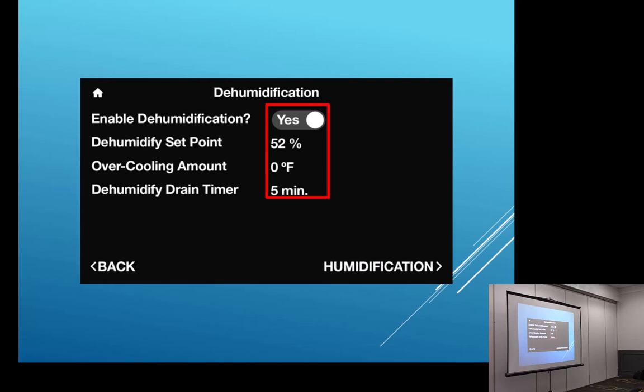So what are you recommending on the enabled dehumidification? If they want to enable dehumidification, I would move it up to 56, 57%. Give us something a little more realistic to shoot for. I've had people come in and set it down to 35%, 45%. If they're looking at that number, it's just not going to happen. And if they want something like that, then you need to offer whole home dehumidification.